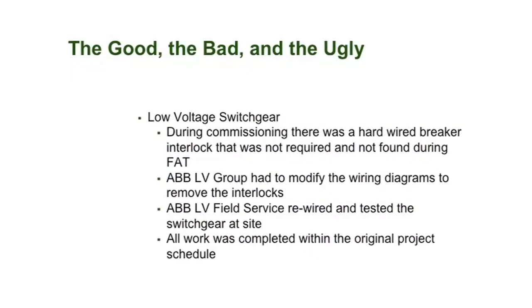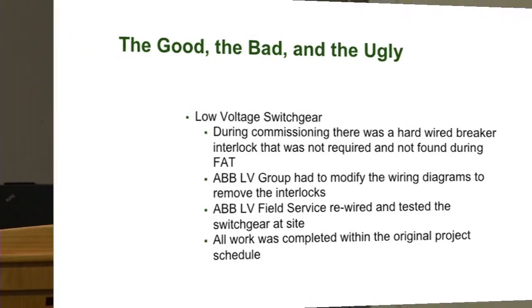The next one is the low voltage switchgear. Even though we completed an FAT of the switchgear at LPS, once we installed it and were doing the final testing on site, we discovered that the main tie main had a hardwired interlock, which was unacceptable to the operation of the plant. I was able to get ABB low voltage field service in, and with their engineers, they corrected the wiring issue on the design documents, and the field service engineer rewired the switchgear at site, completed a thorough testing, and then we re-executed the SAT on site and corrected the problem, and we were able to move on.